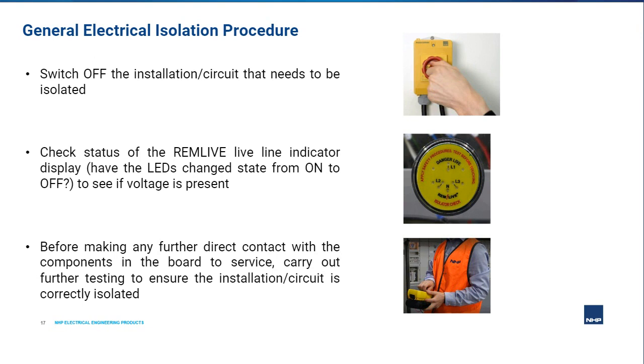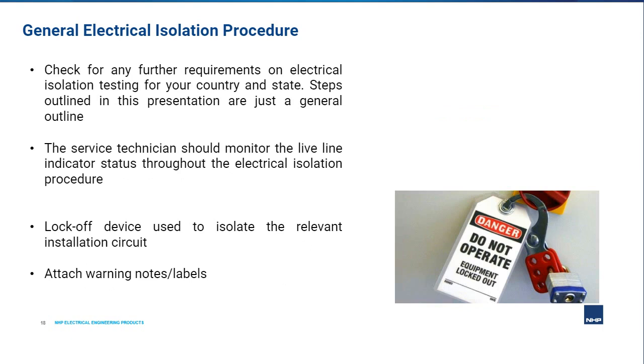It's important to note here that the REMLIVE liveline indicator is not used to bypass any safety procedures and instead provides an extra level of safety to the user as the live visual status is given on the presence or absence of voltage. Another point to add is that measuring live voltage with a multimeter is a hazard on its own. By using the REMLIVE liveline indicator, it gives you an extra level of safety before you use your multimeter.